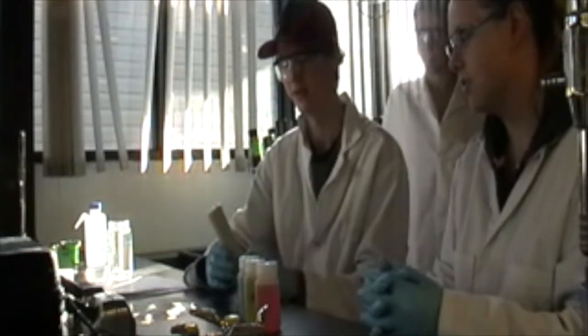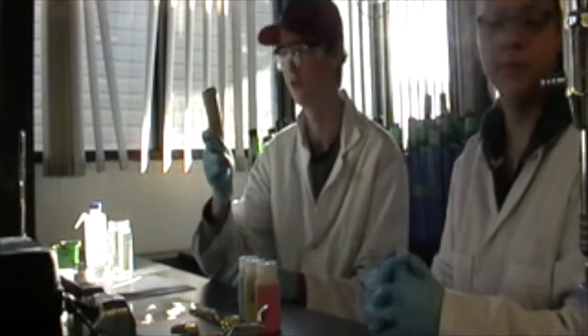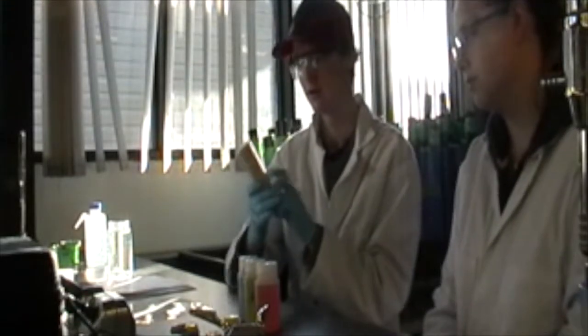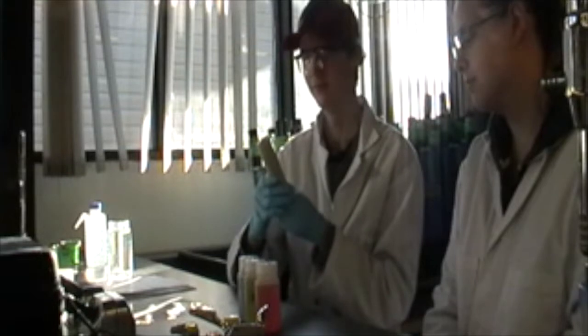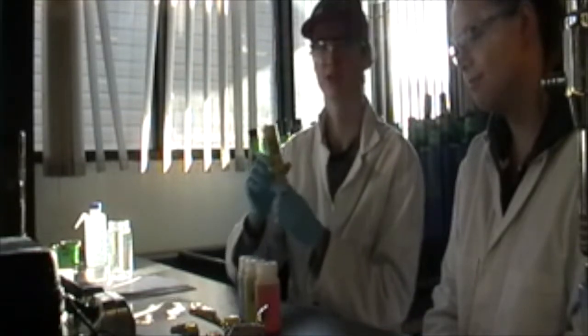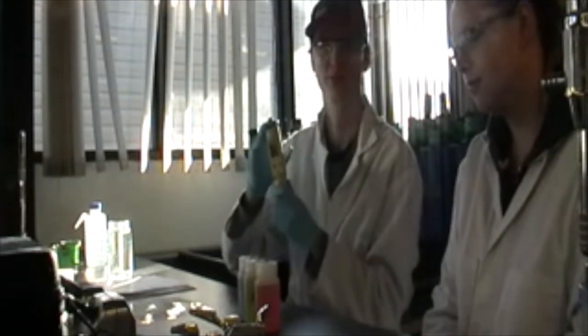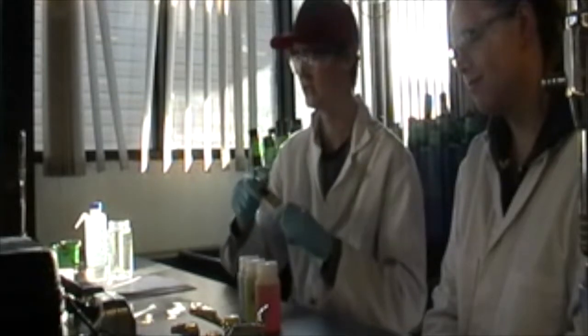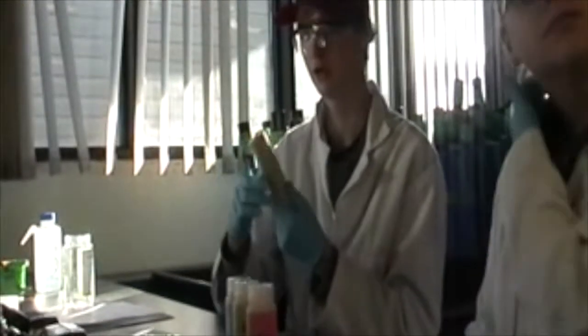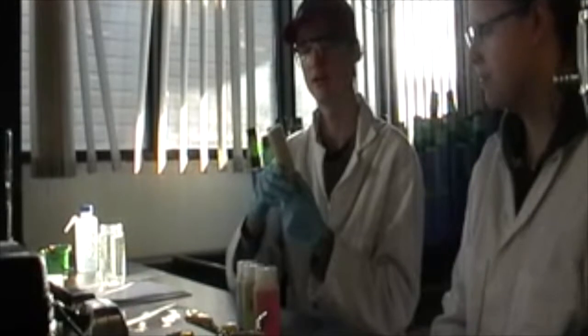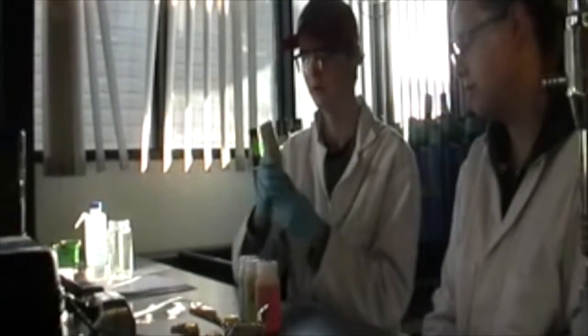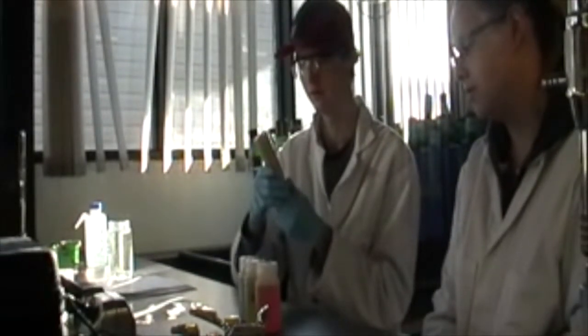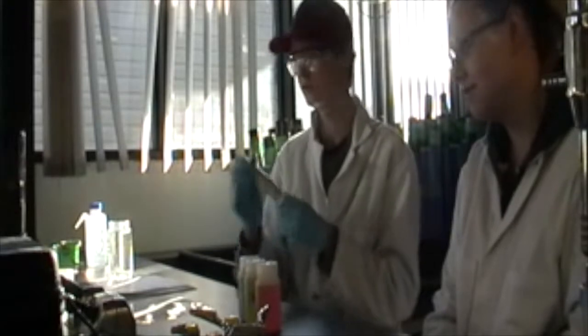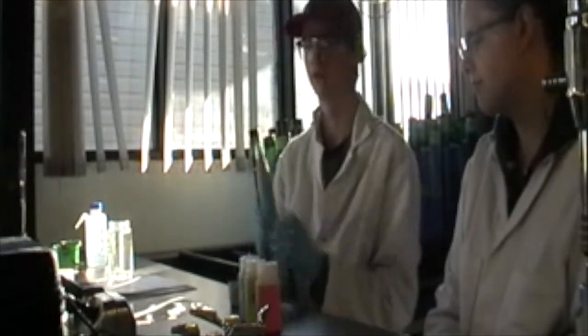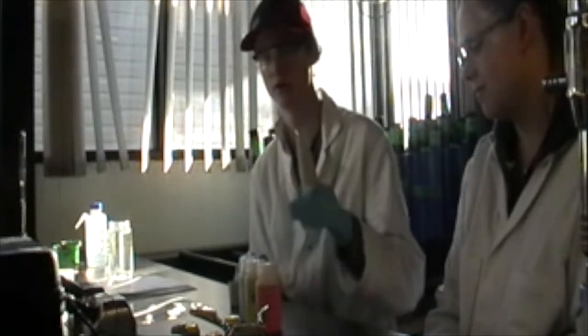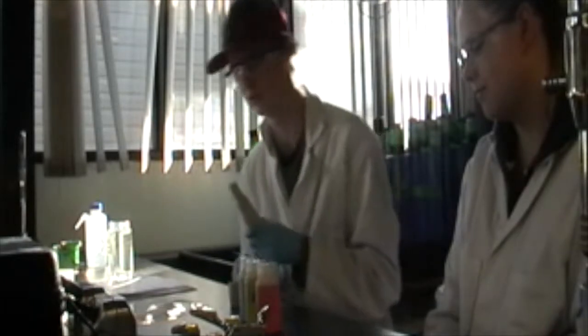And the first test we're going to do is pH. So how we do pH is, the first thing we do, we turn the instrument on, and we make sure we have full battery. And in this instrument, our battery is full, which is great. The second thing we do is clear the standards in the pH meter, which is done for us now. The next step we do is clean this with distilled water before putting it into our known pH solutions.